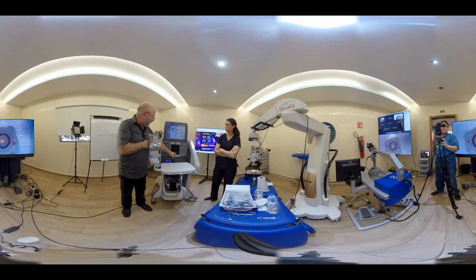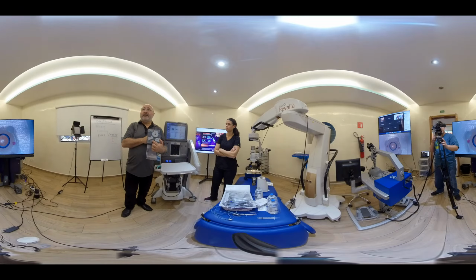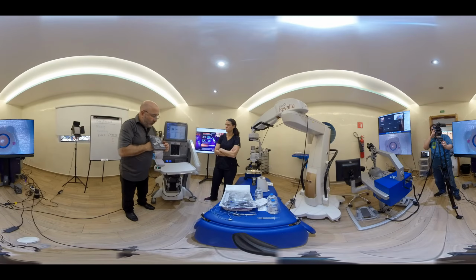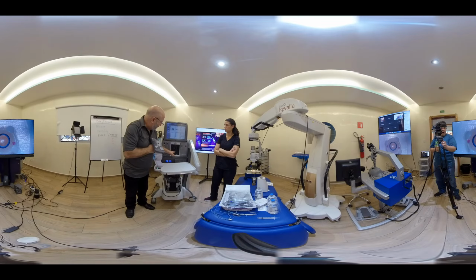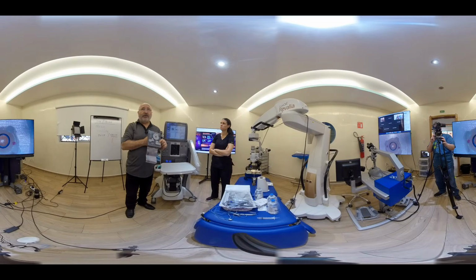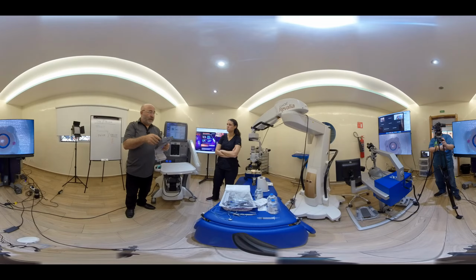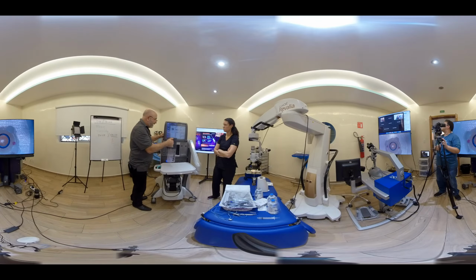We use an ultrasound sensor here that reads two transducers shooting into the infusion line. All these other little notches are controlled by little pistons that close off things like the aspiration flow to the eye or the infusion going to the eye. We have two infusion chambers and one tiny aspiration chamber, which uses a peristaltic pump to feed into the bag. How do we put the cassette in?